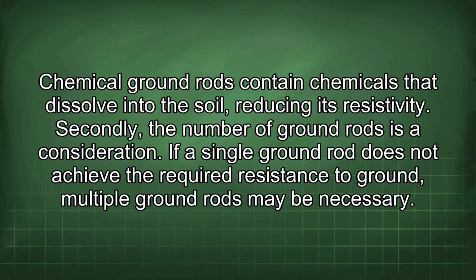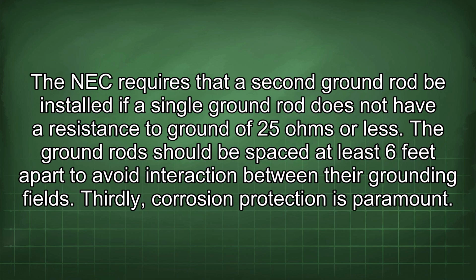Secondly, the number of ground rods is a consideration. If a single ground rod does not achieve the required resistance to ground, multiple ground rods may be necessary. The NEC requires that a second ground rod be installed if a single ground rod does not have a resistance to ground of 25 ohms or less. The ground rods should be spaced at least 6 feet apart to avoid interaction between their grounding fields.